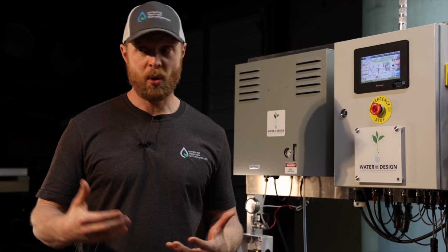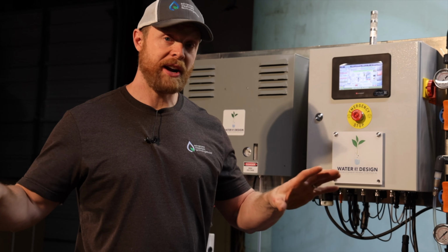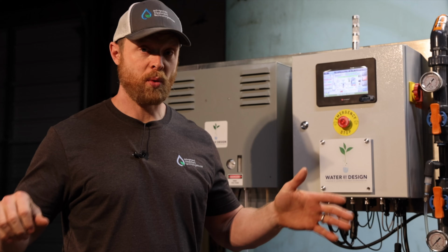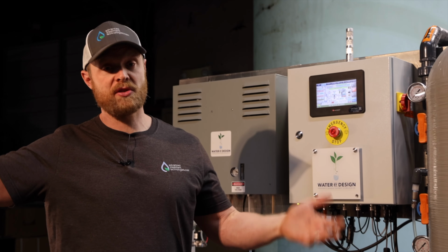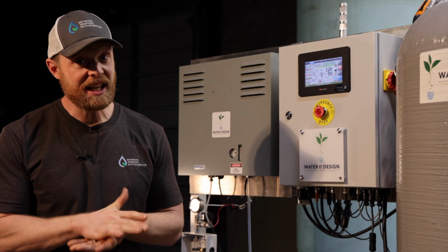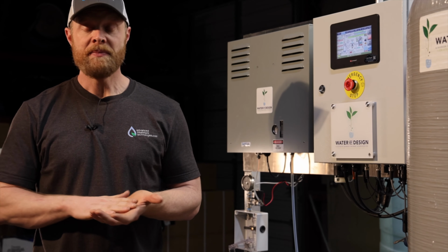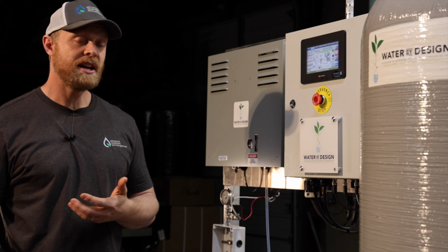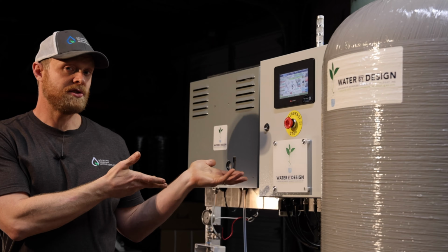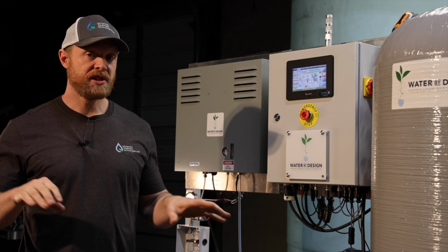This is again why it's important that we're testing and then we're adjusting, because depending on the levels of growth that's happening in those distal lines, your ORP levels could vary pretty dramatically from, say, this week to, say, 2 weeks from now, or maybe even just a week. So again, we have to make sure that we're getting at least 600. More is not necessarily better, but at least 600. And again, if you're not measuring inside that line, then you have no idea what it needs to be adjusted to at the system.